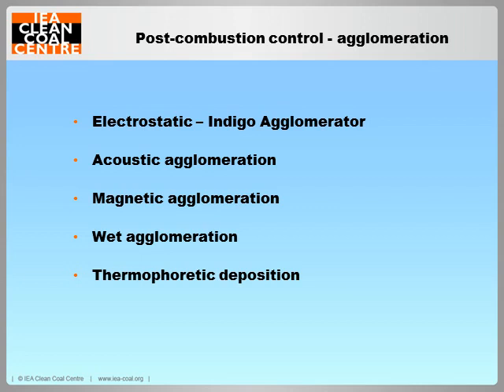Agglomeration can bind fine particles into larger ones, thus making their collection easier. It sounds like a very simple and promising method. However, there are no commercial applications for these technologies at the moment. Indigo Technology of Australia's agglomerator was nearly successful — by 2008 there were eight commercial installations across Australia, the USA, and China. Unfortunately, the company went into liquidation in February 2011. Some experts regard bipolar electrostatic agglomeration with ESP as an alternative to hybrid ESP and fabric filter technology.